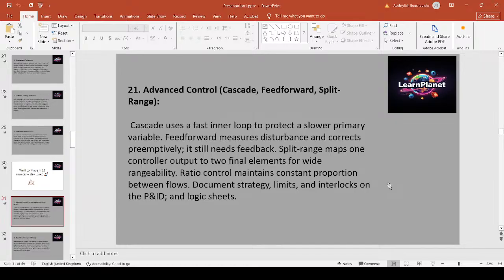Okay, guys, let's continue with the 21st topic. Advanced control: cascade, feedforward, split range. Cascade uses a fast inner loop to protect slower primary variables. Feedforward measures disturbance and corrects preemptively. It still needs feedback. Split range maps one controller output to two final elements for wide rangeability. Ratio control maintains constant proportion between flows. Document strategy, limits, and interlocks on the P&ID and logic sheets.